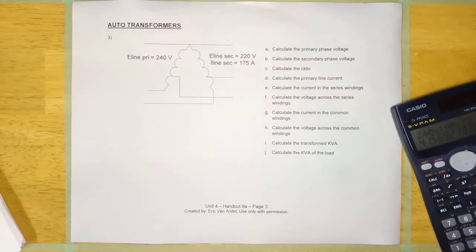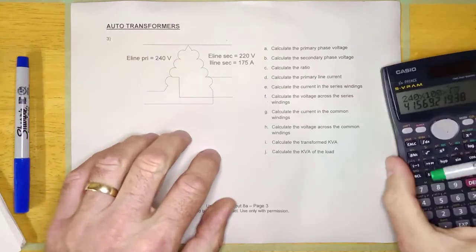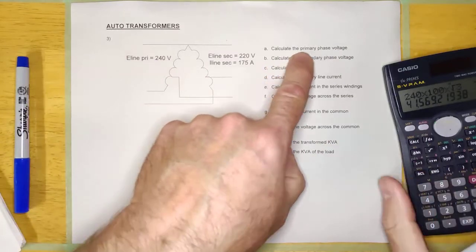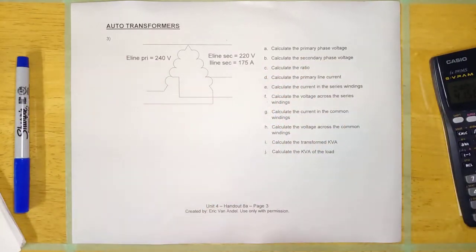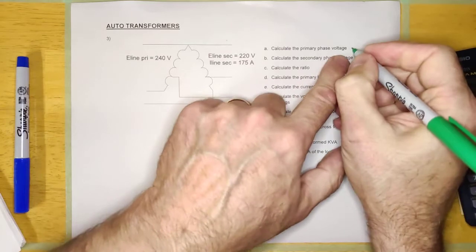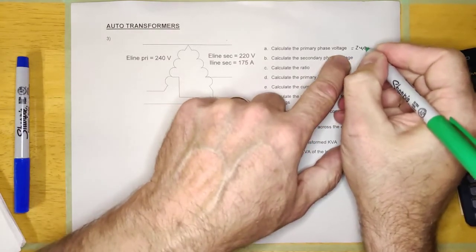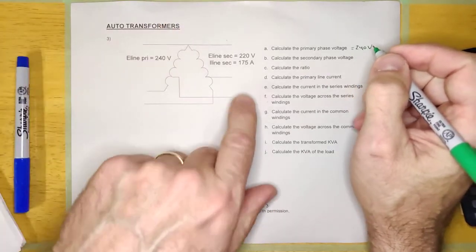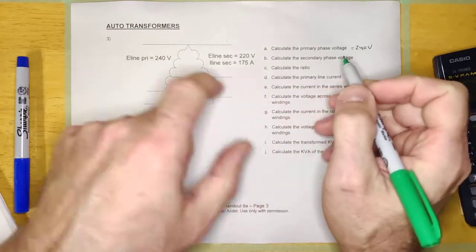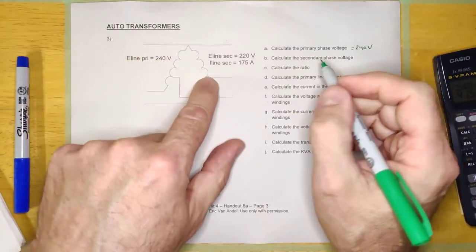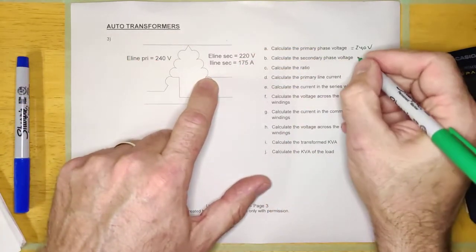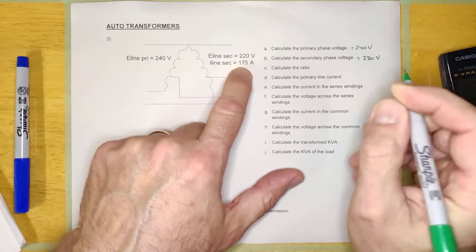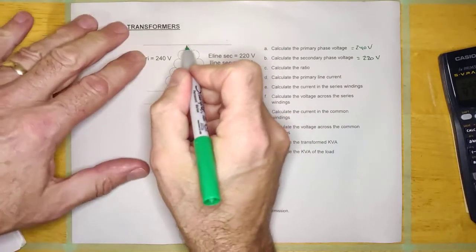It says here, look at E-line primary is 240 volts. Calculate the primary phase voltage. Well, this is a delta transformer, E-line equals E-phase, so this is simply 240 volts. If this is 240 from here to here, then it's going to be 240 from here to here. Calculate the secondary phase voltage. Well there it is, it's delta so it'll be the same as the line voltage, 220 volts.